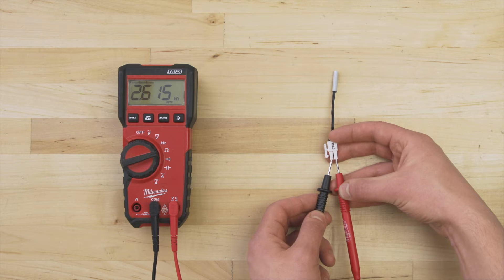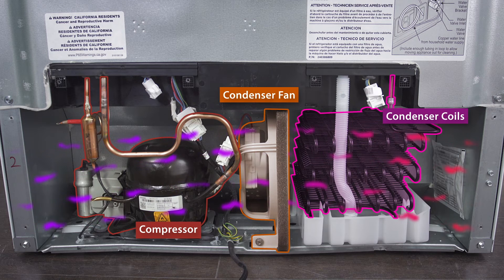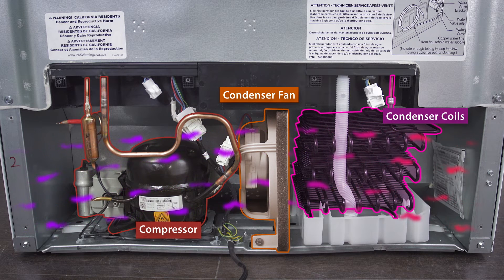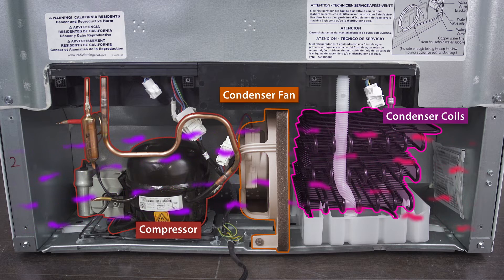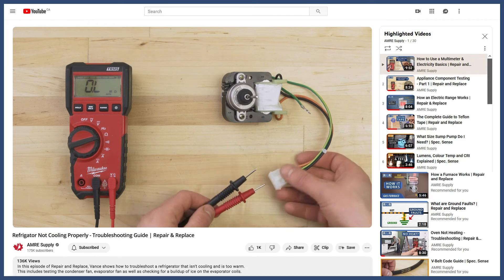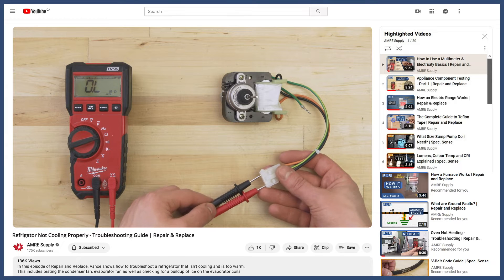The temperature sensor is also known as a thermistor and can be tested with a multimeter. Additionally, a faulty condenser or evaporator fan can prevent the system from cooling properly. You can learn more in the troubleshooting video linked below.